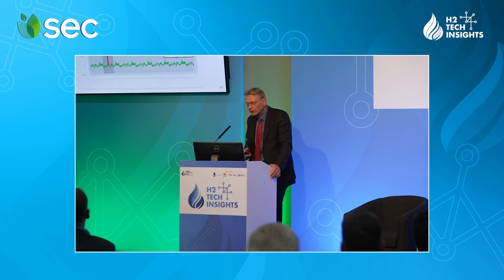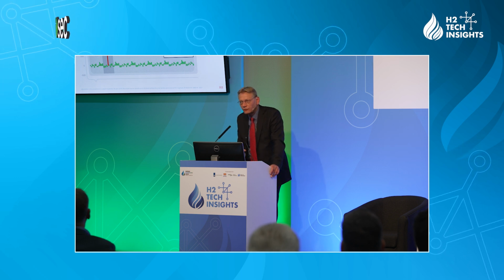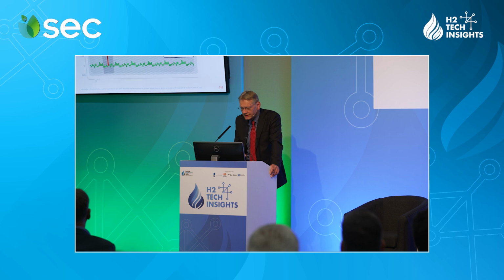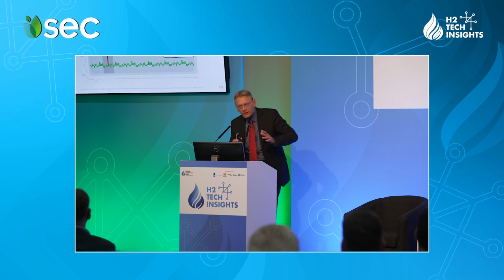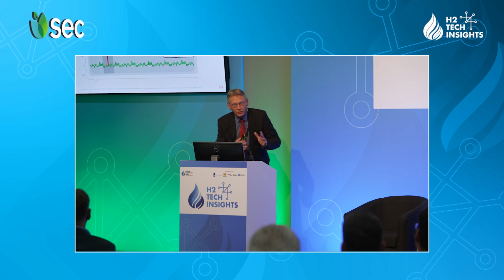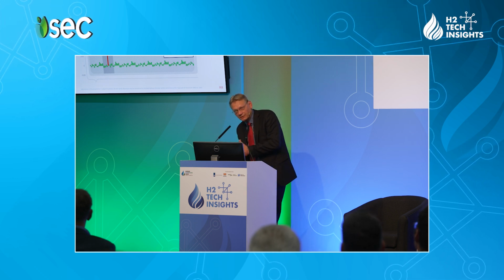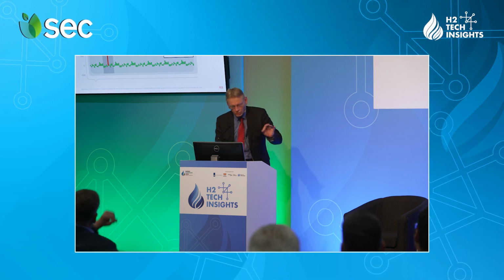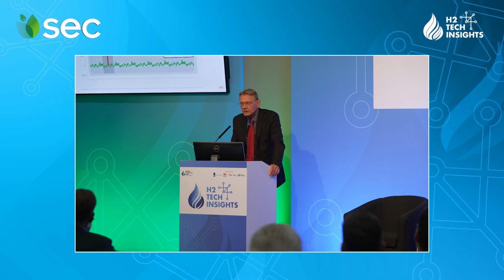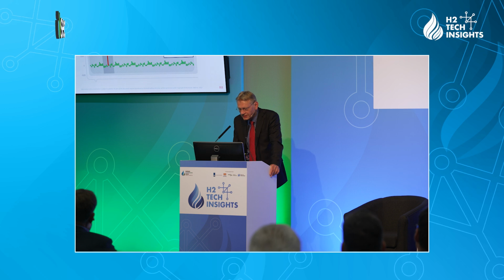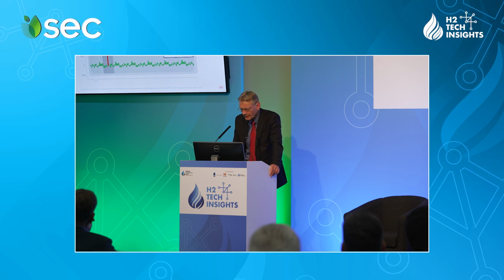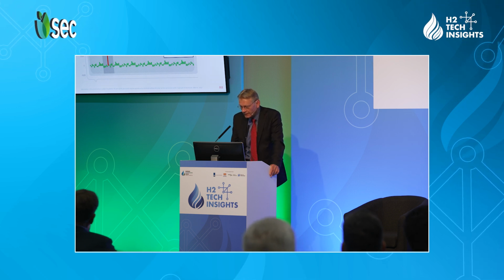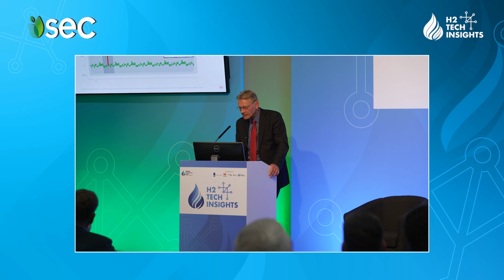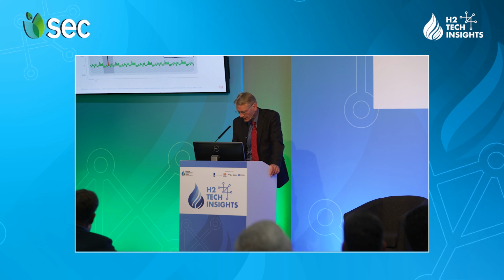The solution is what we call residuals, generated by a software that we call EMOS Early Detection Engine. The plant operator is looking at the difference between a predicted voltage coming from a neural net and the measured. If the difference is zero, all good. The neural net is built during the startup, so you have automatic neural net training during startup. And then you can see an alarm whenever a cell turns into a black sheep like this one.